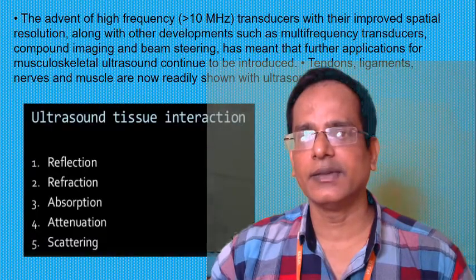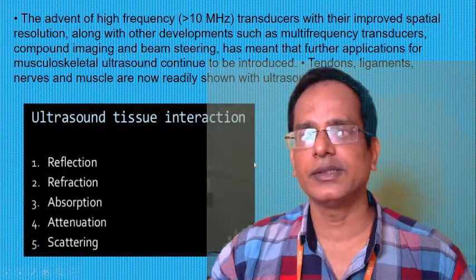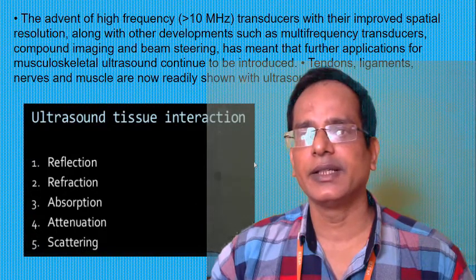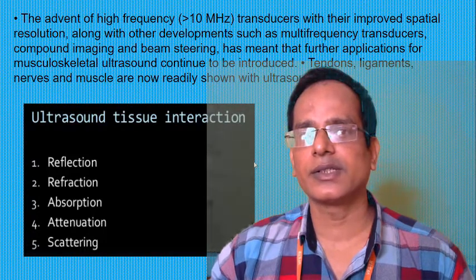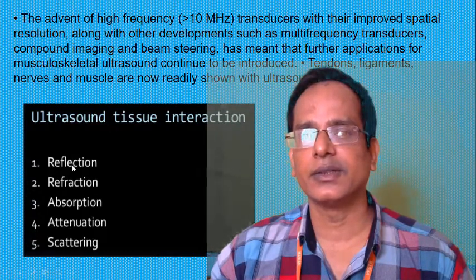The advantage of high frequency — using above 10 MHz — is improved spatial resolution, generated by the transducer. Developments such as multi-frequency transducers, compound imaging, and beam steering have further extended the applications of musculoskeletal ultrasound. Tendons, ligaments, nerves, and muscles can now be shown by ultrasound.